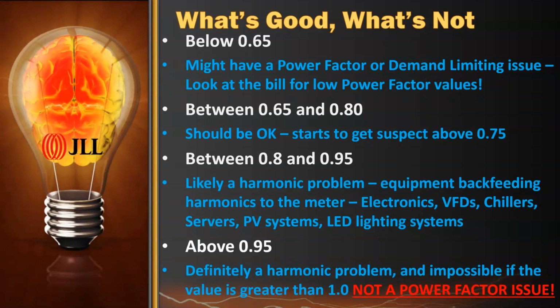So you paid for it going in, the equipment does some stuff, generates a signal, goes back to the meter, and the meter looks at it and goes, hey, I'm going to count that. Most meters do a very good job of counting it. And this is not power factor. It is not. This is something else completely. It is a harmonic signal that's being generated inside the building.